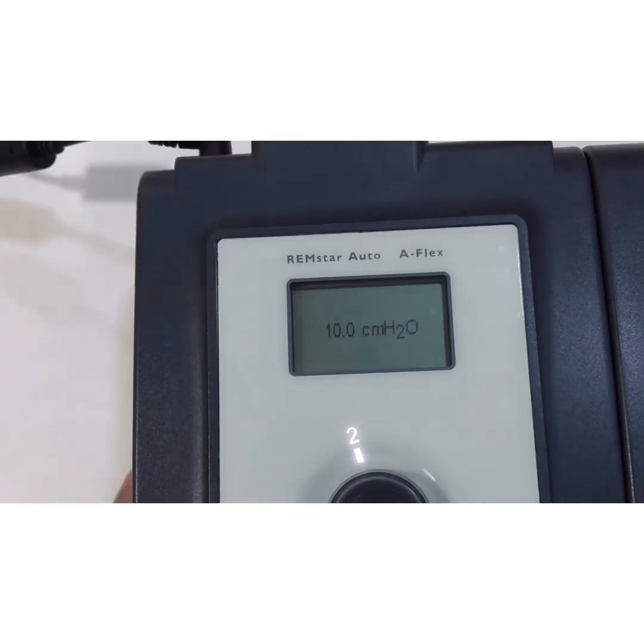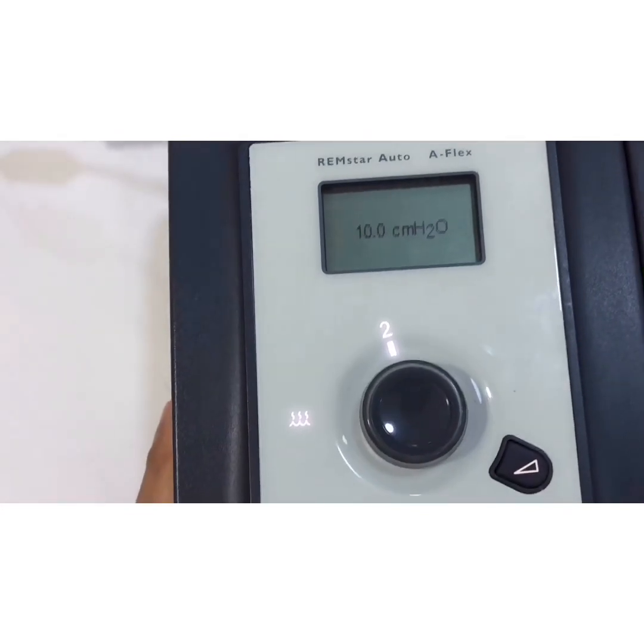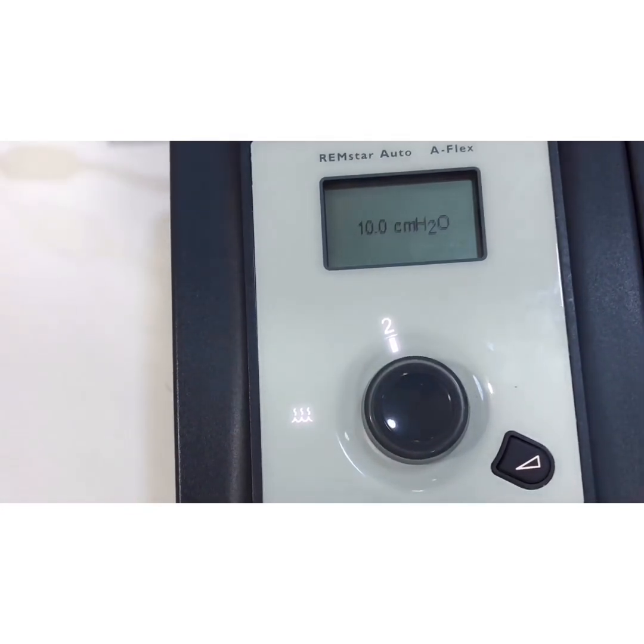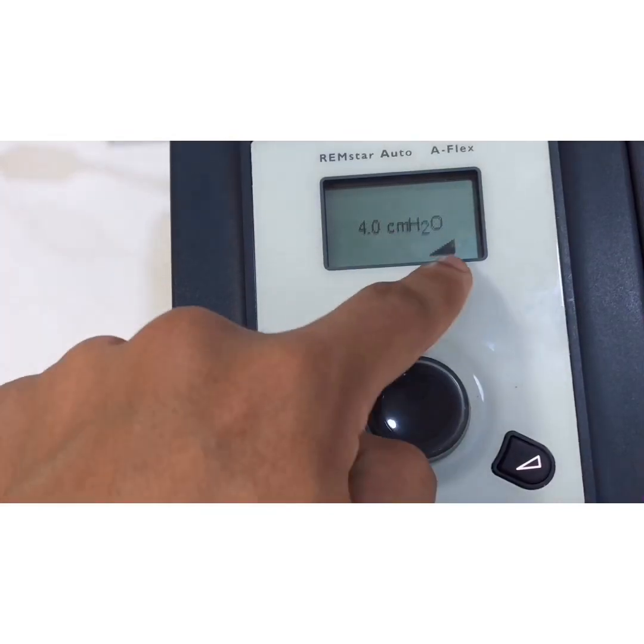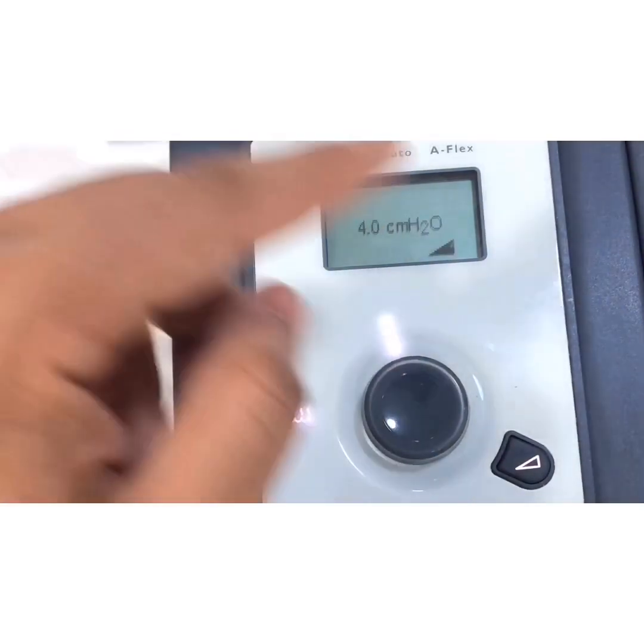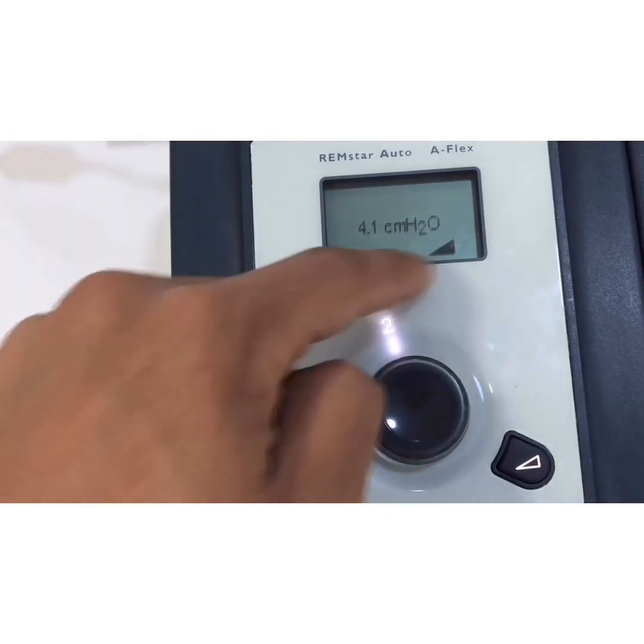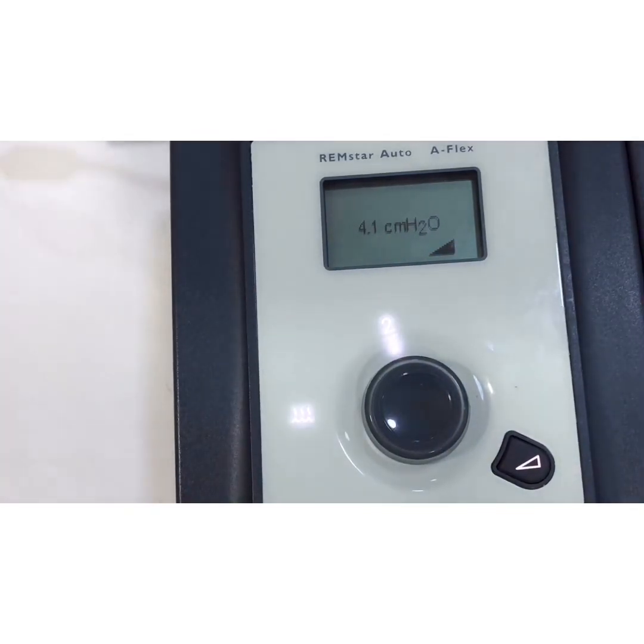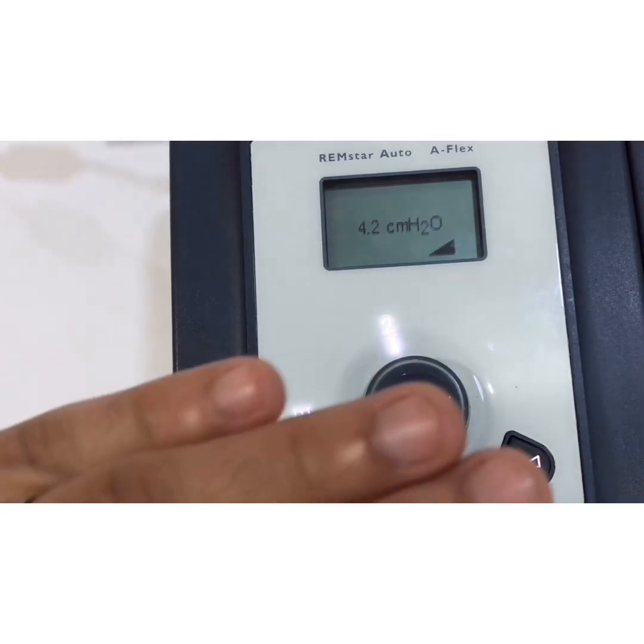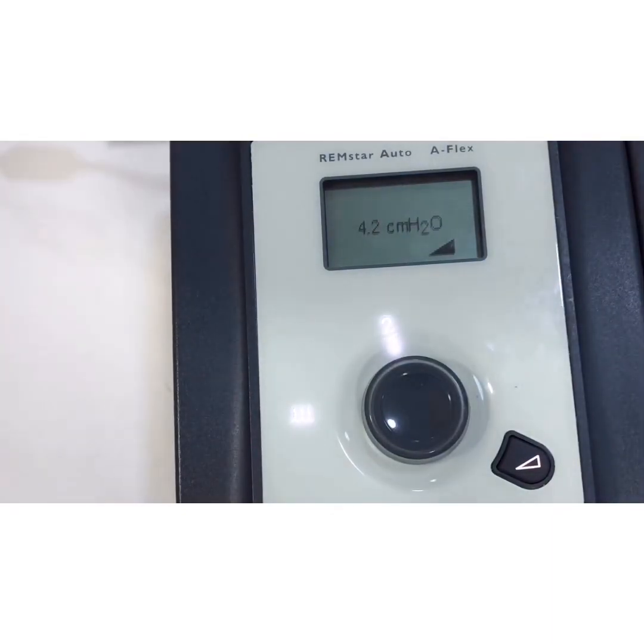So one more thing: we can set the ramp, but it doesn't mean it's going to work. We have to activate it, and the only way to activate it is when the therapy is on. So just press. As you see, the pressure drops from 10 to 4, plus we have this sign of ramp. That means the ramp is activated, and now the pressure will rise gradually till we reach the preset pressure. I cannot deactivate it from here. All I have to do is stop the treatment and restart it. So now the ramp is not activated.